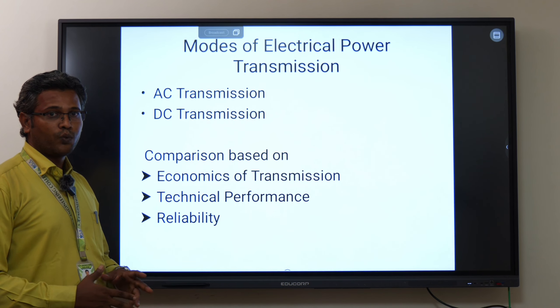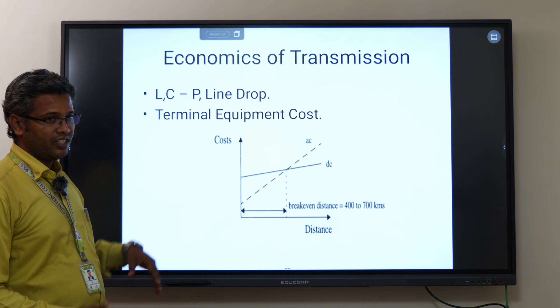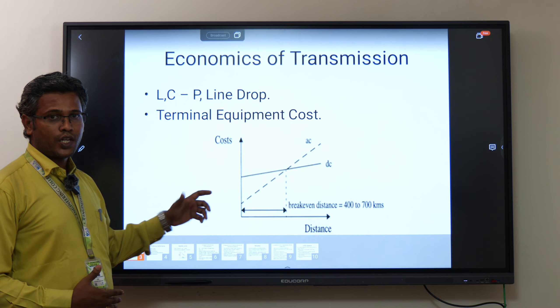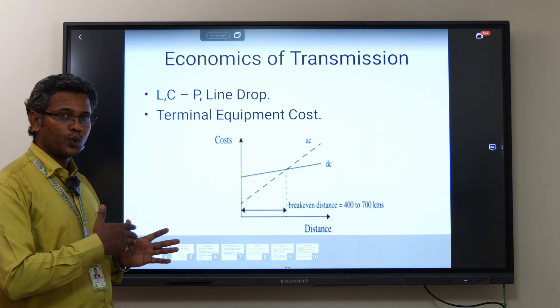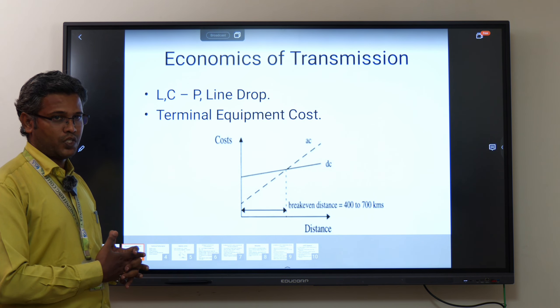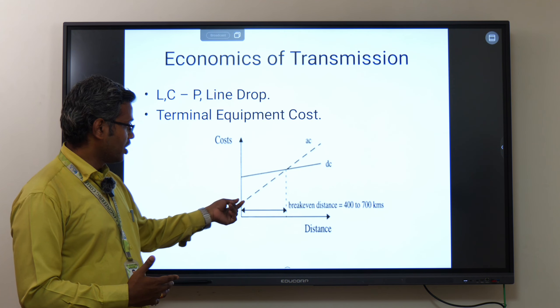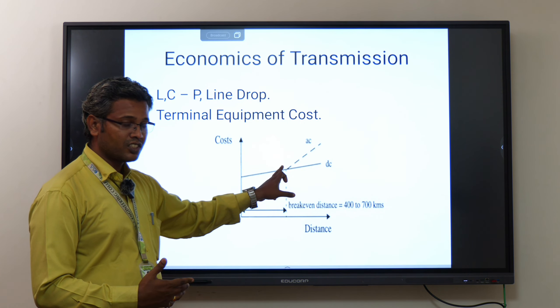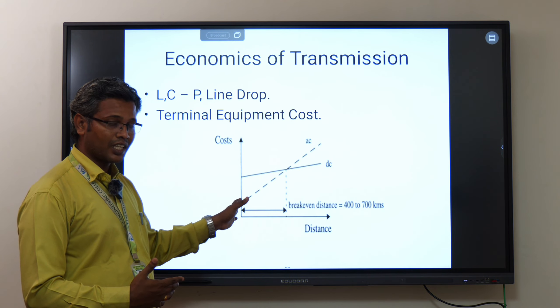First, we consider economic considerations — which one is more economical? With a simple graph, it is clear that cost versus distance is the key factor. For short distances, AC transmission is preferred. For long distances — for example, about 700 kilometers — DC transmission is preferred. Up to the break-even distance, the cost of AC transmission is less compared to DC.